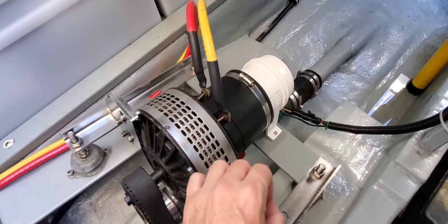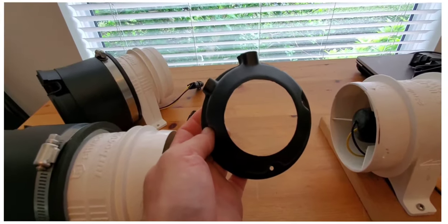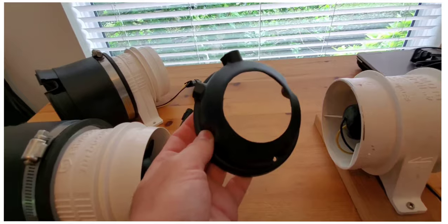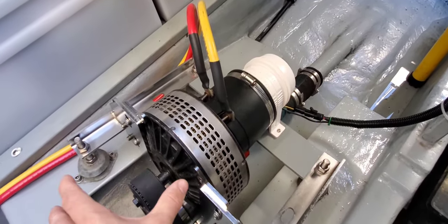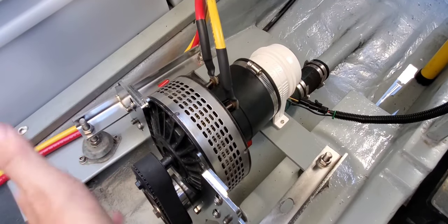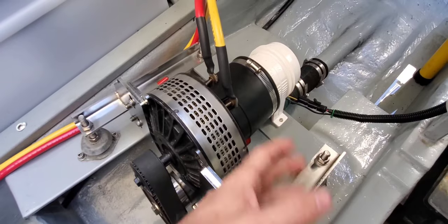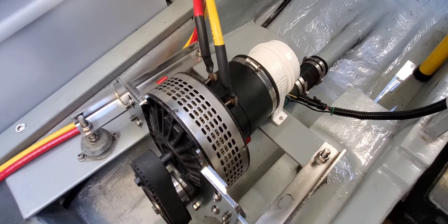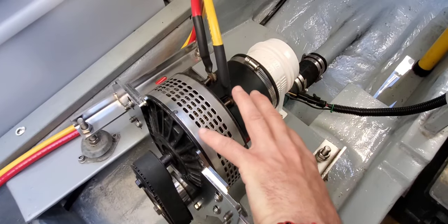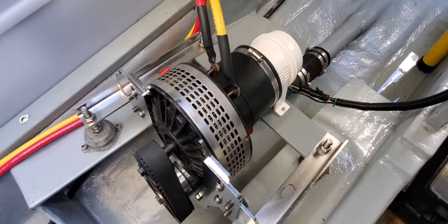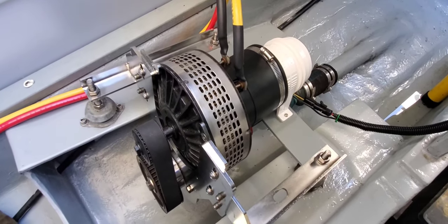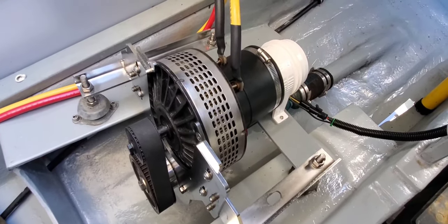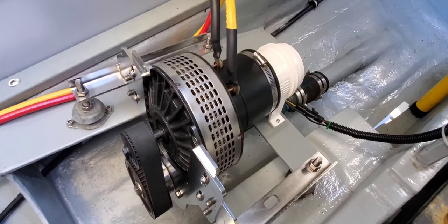What we did is drill a hole with a hole saw through that plastic cover and fix the blower fan here at the back. So when we feel the motors might require a little bit of extra airflow, a little bit more assistance, we just turn these blower fans on and that blasts fresh air onto the brush holder where the brushes are in contact with the commutator. The faster these motors spin, the hotter they're going to get, and that's just simply because it's a brushed DC motor.